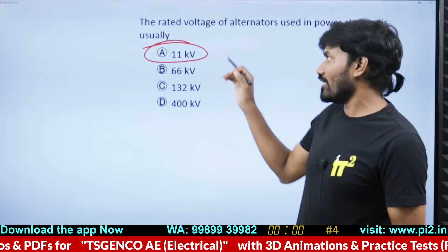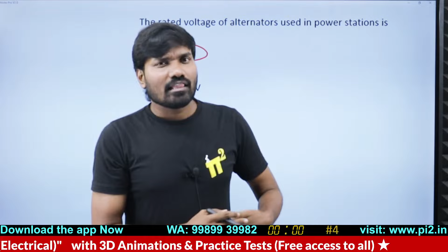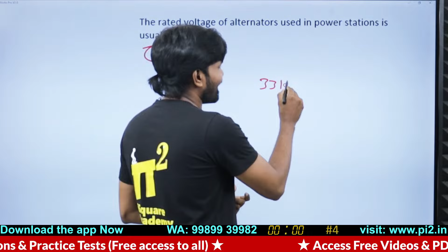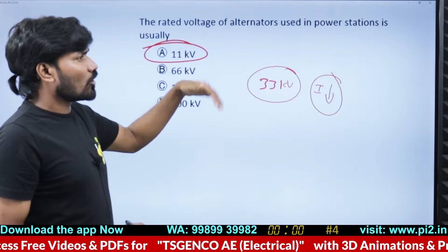Now the question is, why are you limiting this generated voltage to 11 kilovolts? Why can't you generate 33 kilovolts? Because if you increase the voltage for the same capacity of power, current will be less, losses will be less, copper size will be less. But still, why are you limiting your voltage to 11 kilovolts? Why not beyond 11 kilovolts?